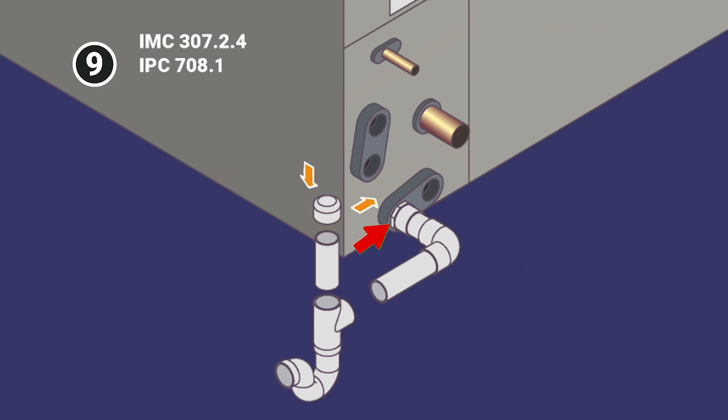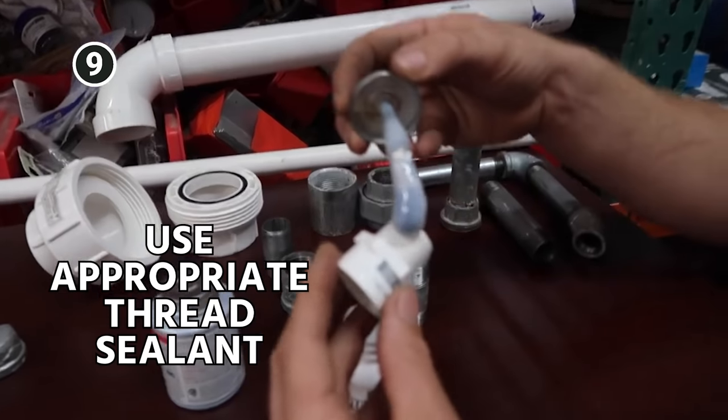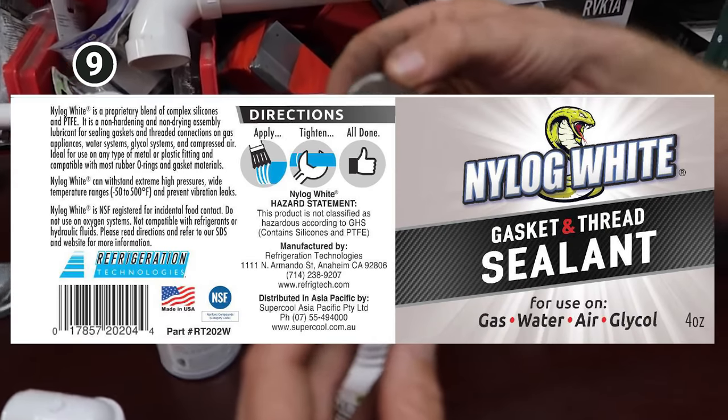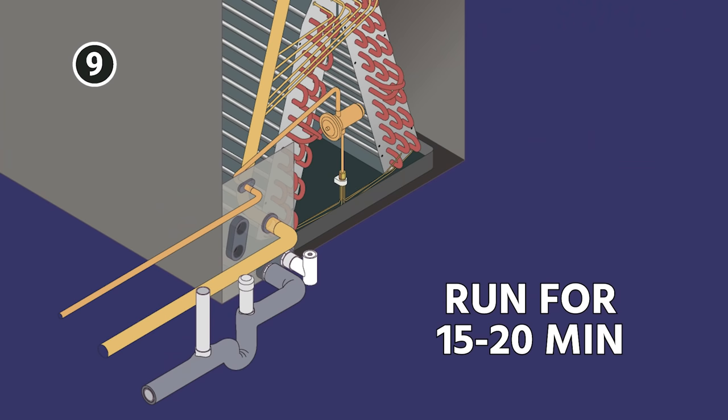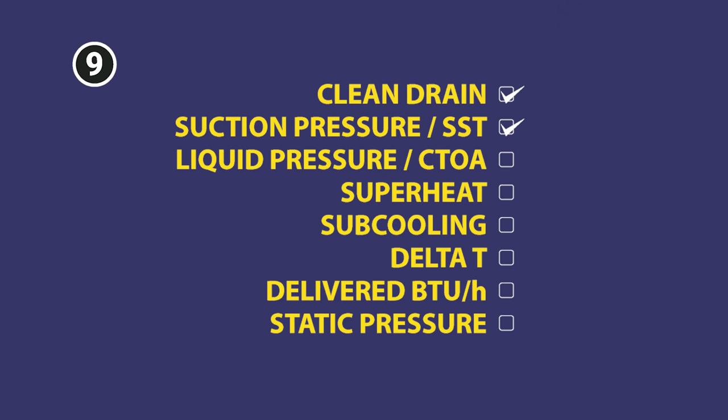Also, when you do reattach your drain line to the evaporator coil, I forgot to mention that, you want to use a good pipe dope such as Nylog White to make sure that you get a good threaded seal into that drain pan. Once you let it run 15, 20 minutes, then go ahead and measure your suction pressure, otherwise known as your suction saturation temperature, because it's really the temperature you're looking for. Your liquid pressure, which shows you your condensing temperature over ambient. Superheat, subcooling, delta T, and then to even be more thorough, do your delivered BTUs per hour, which is easy to do with MeasureQuick, and measure your static pressure.